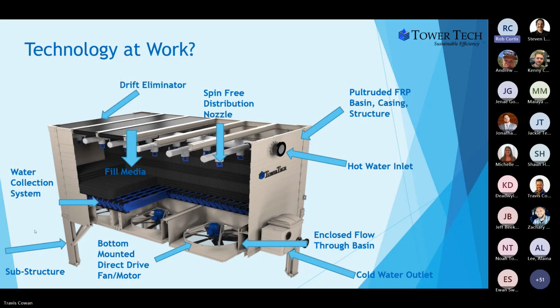And then lastly, we have the cooling tower structure, the basin, the casing of the cooling tower. Actually, the whole cooling tower is made from an inert material, so it's non-corrosive and gives you greater longevity. So our basin, our casing, our structure is made from pultruded FRP. All the other components are made from a polymer material, whether it's the fill material, the water collector, the nozzles, things of that nature. And the only thing metal on the tower is our hardware, which is 304 stainless steel, and our mechanical equipment support for the fans and motors, which again is 304 stainless steel. So you get the longevity of a product life that is not going to be susceptible to the corrosion that happens with a metal piece of equipment.